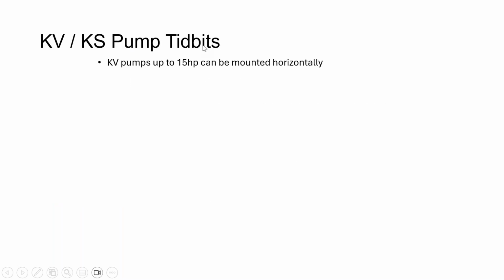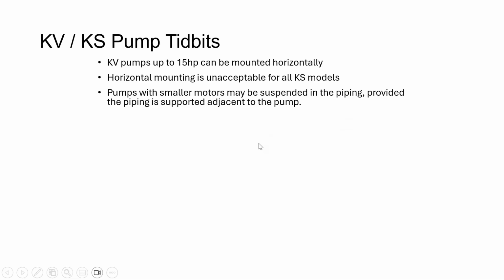So here's some of the tidbits for these models, okay? KV pumps, up to 15 horse can be mounted horizontally. To be quite honest, I don't see that too often, but it can be done, all right? Most of the time, I see them all mounted vertical, right? But up to 15 horse you can mount them horizontally. You cannot mount any of the KS models horizontally. They always have to be mounted vertically.